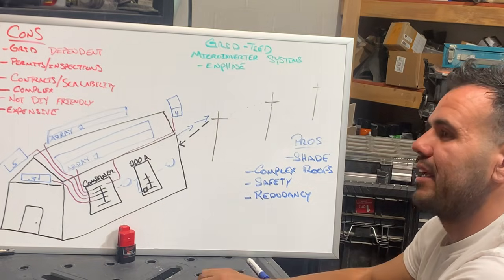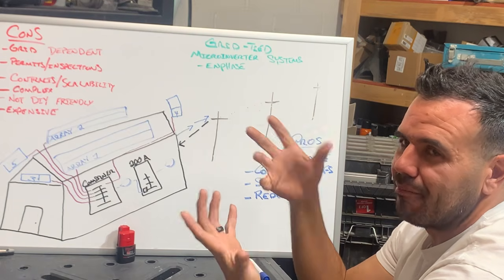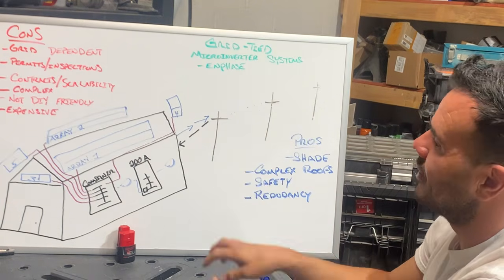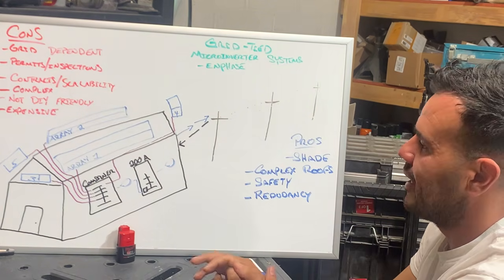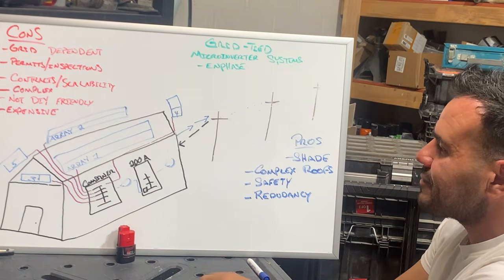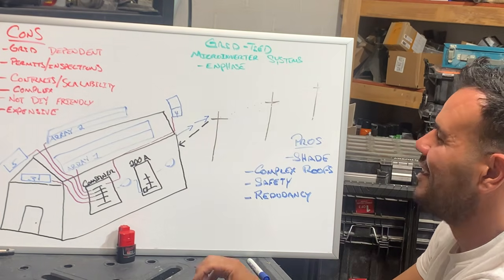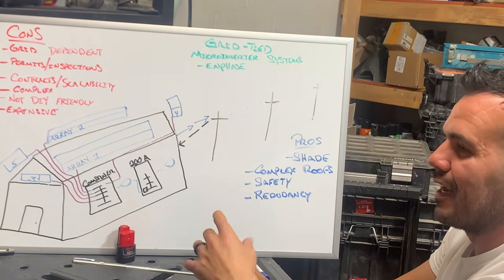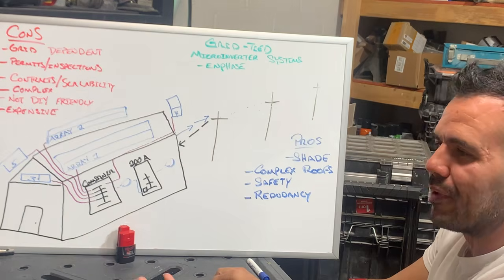Now inside that inverter, there's a component called an MPPT, a maximum power point tracker. The job of that component is to take into account the voltage that's coming in from this array, so 400 volts, the amperage, 10 amps, and the temperature. It'll optimize all those to give you the max amount of wattage, 4,000 watts, ideally. It doesn't actually work that way, but just to get a rough idea, that's generally the concept. And so we have 400 volts, 10 amps coming down from our solar array going into our MPPT, and then our MPPT is going to fire out 4,000 watts that we can use.